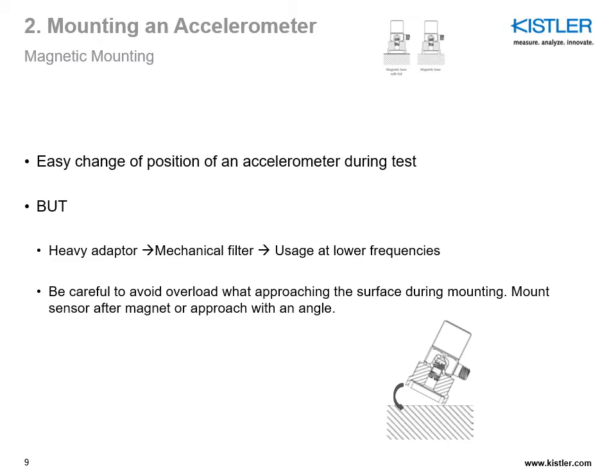Magnetic mounting is also well appreciated whenever a ferromagnetic surface is involved. It's convenient because you can move the sensor around very quickly. However, magnetic mounting is very heavy, which can significantly affect the frequency response of the sensor. In addition, it's very dangerous for the sensor itself. Whenever a magnet is being used, we recommend first mounting the magnet on the surface and then the sensor on the magnet. If this is not possible, approach the surface with an angle. Try not to drop the sensor and magnet directly onto the surface, as such a sharp metal-to-metal impact can be deadly for the electronics inside the sensor.